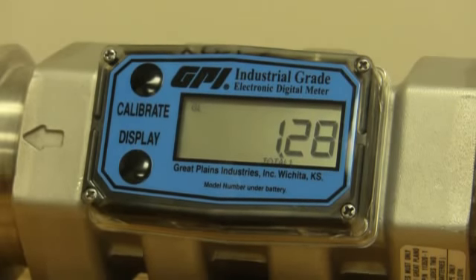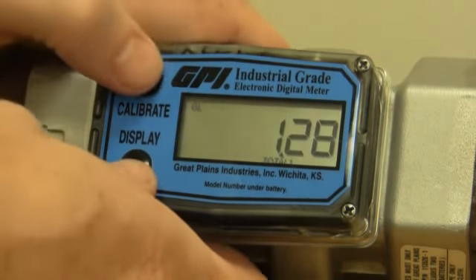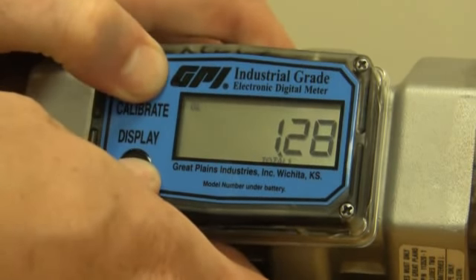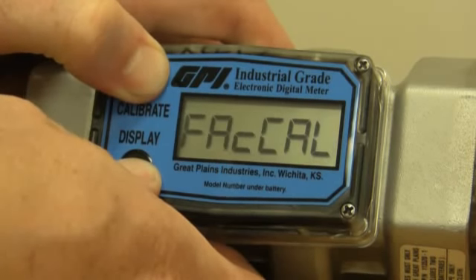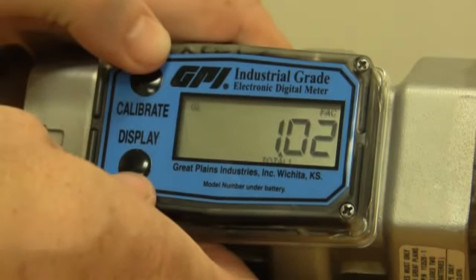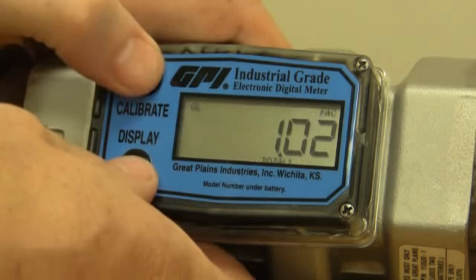Now let's say you've been using it for a few days, and all of a sudden you're going to put water through it, and you want to get back to the factory calibration. You just hold down both buttons, just keep holding them, and then it'll say FAC cal, meaning you're going back to the factory calibration. So when I let go, we're back to the factory calibration. You can tell, once again, because it says FAC up in the top corner.